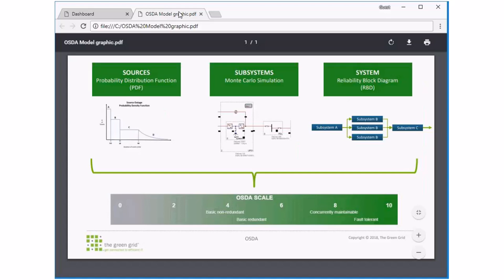OSDA is based upon three different models. The energy sources are modeled using a probability distribution function of the frequency of outages compared to the length of each outage. The great thing about this is that as we model different lengths of energy storage within the tool, we're able to apply this to the PDF and figure out what the downstream availability is. Subsystems are modeled using Monte Carlo simulation, and we also use reliability block diagrams to pull the subsystems together.